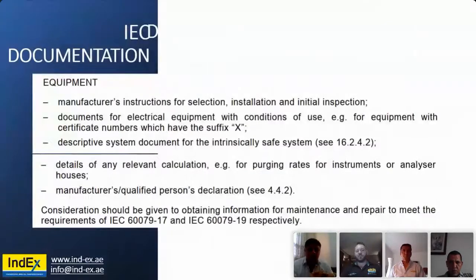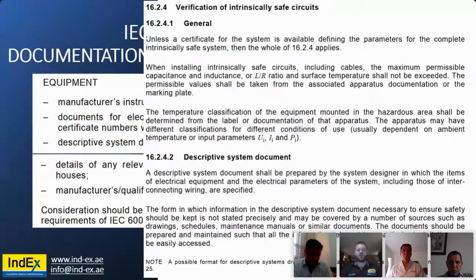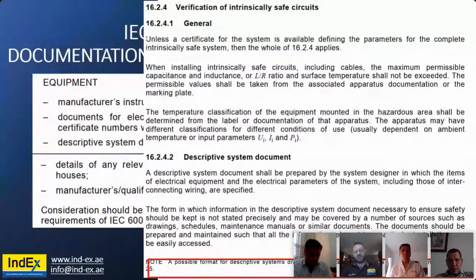Now, the next step of part IEC documentation is the equipment and the manufacturer's instructions, documentation such as the certificate, any relevant calculations, and manufacturer's qualified persons declarations. So what does that look like? Well, for intrinsically safe, we need to verify those intrinsically safe circuits, and it calls for a descriptive system document, which is called for in that note down there to IEC 60079-25.